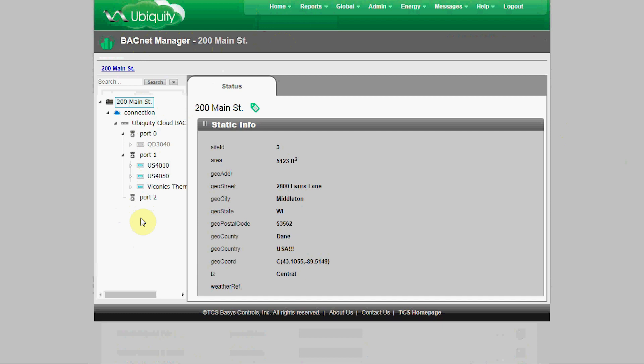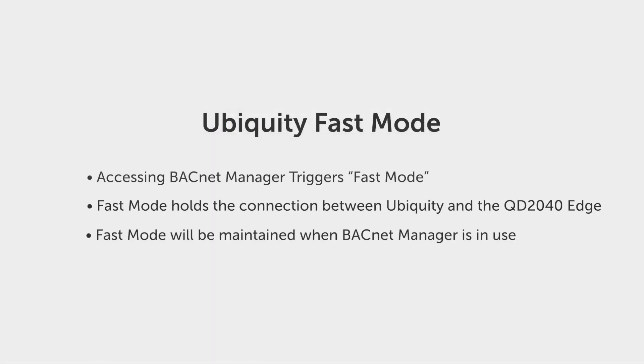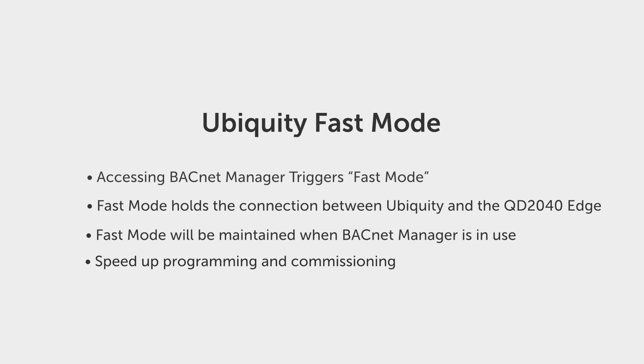This will load a navigation tree. Those of you familiar with other BACnet software like Chipkin or Niagara may be familiar with this type of navigation. Going to the BACnet Manager also triggers the fast mode, so the next time the QD 3040 edge device connects to Ubiquity on its normal one-minute polling cycle, being on the BACnet Manager will trigger automatically and hold the connection while the BACnet Manager is being used.